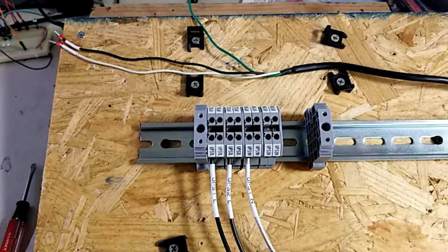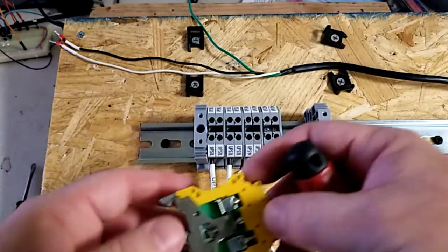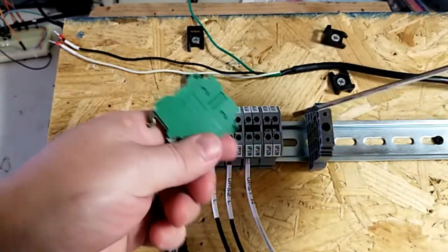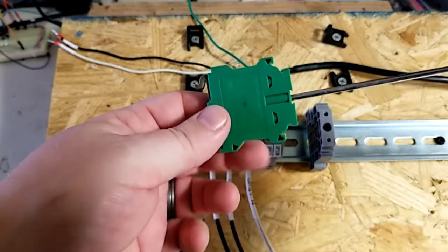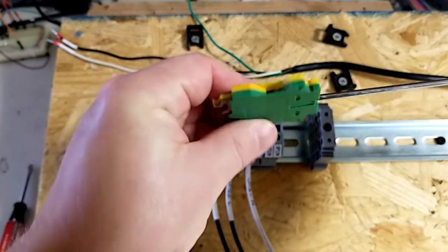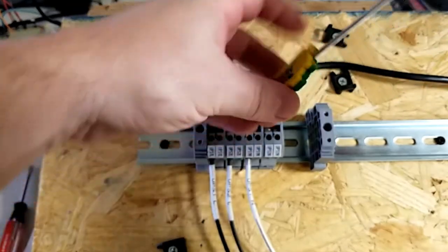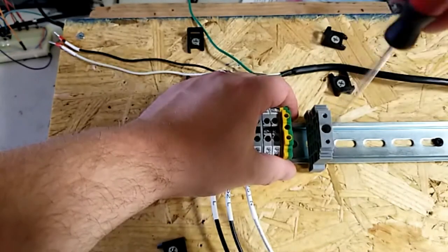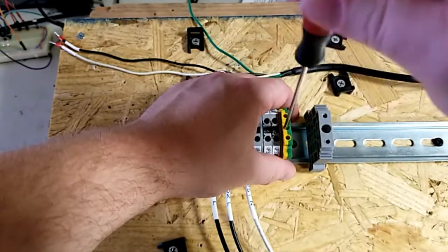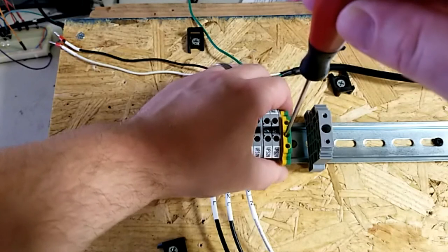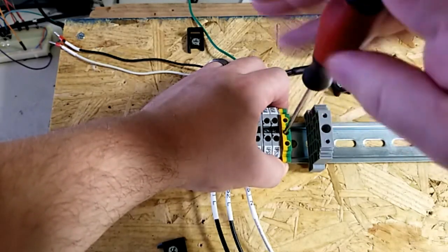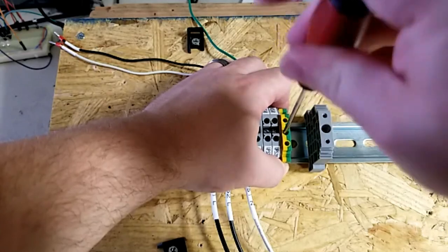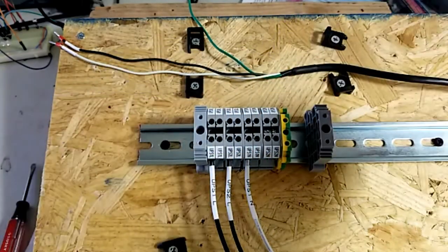For the remainder of these terminals, we're going to use grounding blocks. So these grounding blocks, you'll again use your precision screwdriver. They have a screw right in the center of them that you use to tighten or loosen this. So this guy will also clip on to the rail, but you might need to loosen this screw to actually get it to go down on the rail. Once you're down on there like so, then you can tighten the screw down and it will clamp itself on. This should be clamped on very tight then.